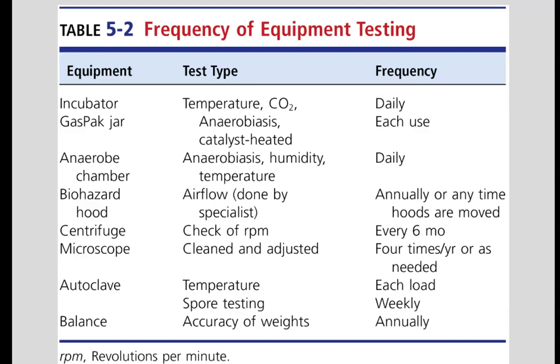Biological safety cabinets get checked at least annually. If for some reason you are moving the hood, then all that has to be checked again — there are people that come and do that, not you. You typically have the HEPA filter changed at the same time, if you're smart.